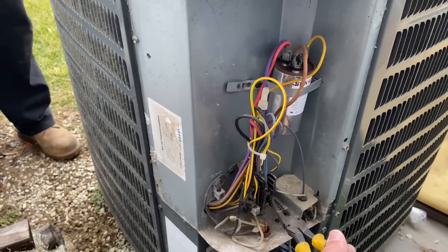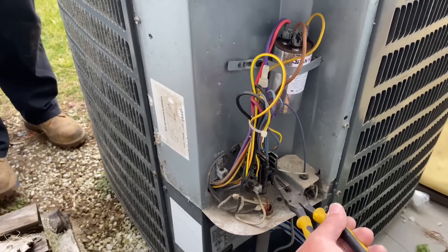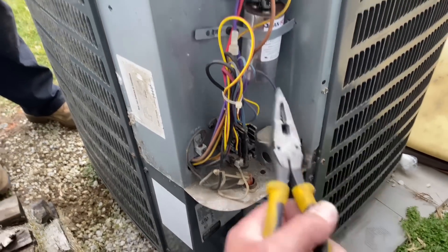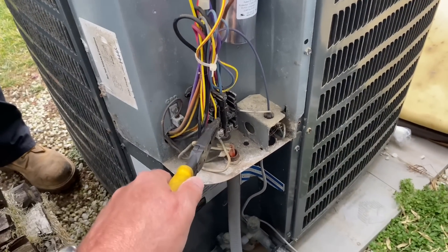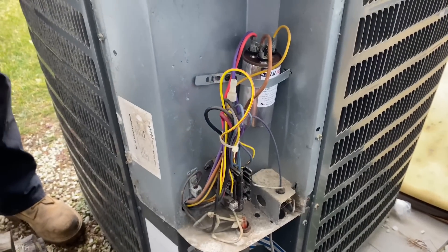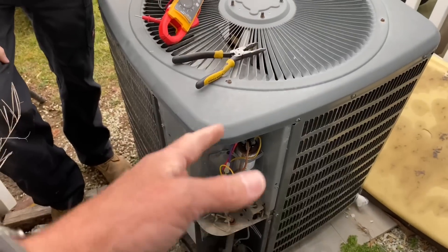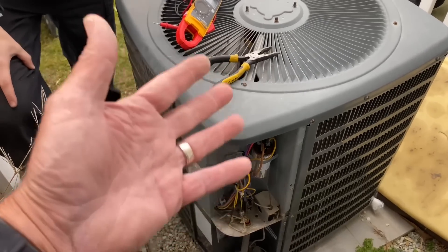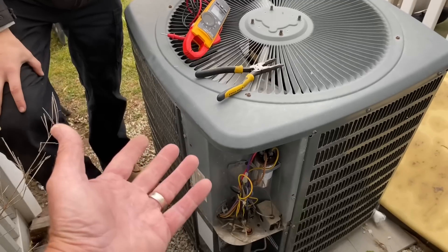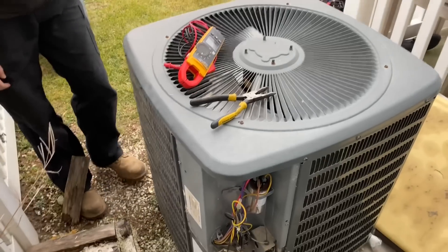We could also test amperage right now, but it's not a great idea because the indoor fan is in unknown condition. I just want to confirm we connected all the wires back properly on the contactor and the capacitor. We did — we're good. My suggestion is to preventatively replace this unit, but it's still in good operating form.